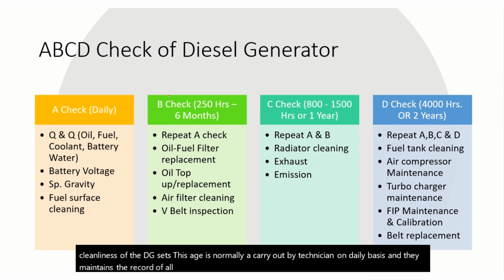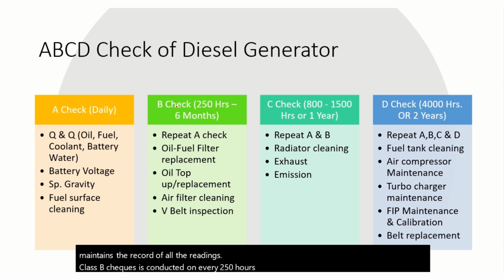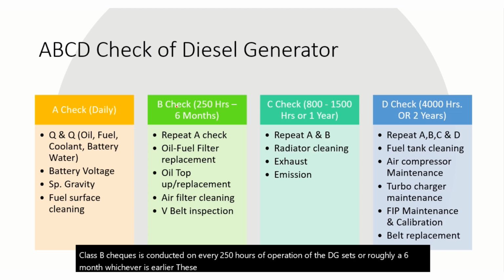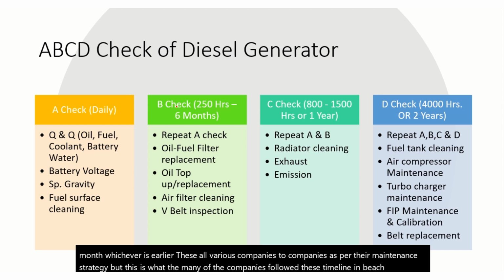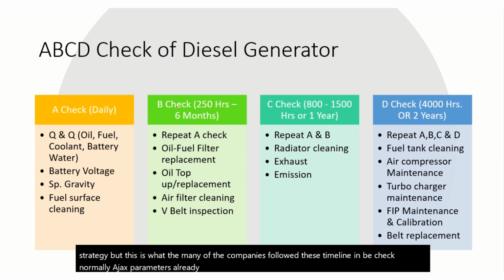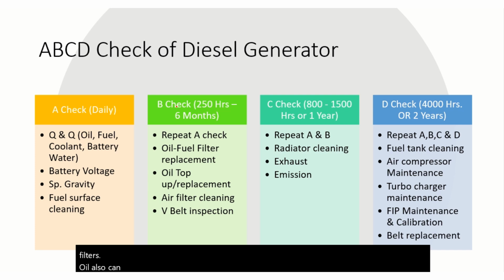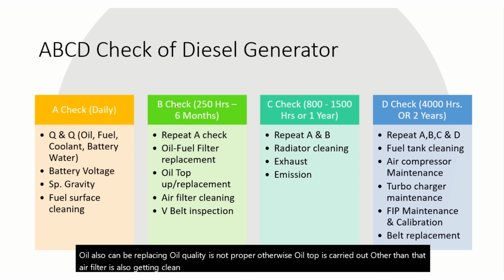readings. Class B check is conducted every 250 hours of operation of the DG sets, or roughly 6 months, whichever is earlier. This all varies from company to company as per their maintenance strategy, but this is the timeline many of the companies follow. In B check, normally the A check parameters are already covered. Other than that, there is a replacement of oil and fuel filters. Oil also can be replaced if oil quality is not proper, otherwise oil top up is carried out. Other than that, the air filter is also cleaned and there is inspection of the belts and hoses.